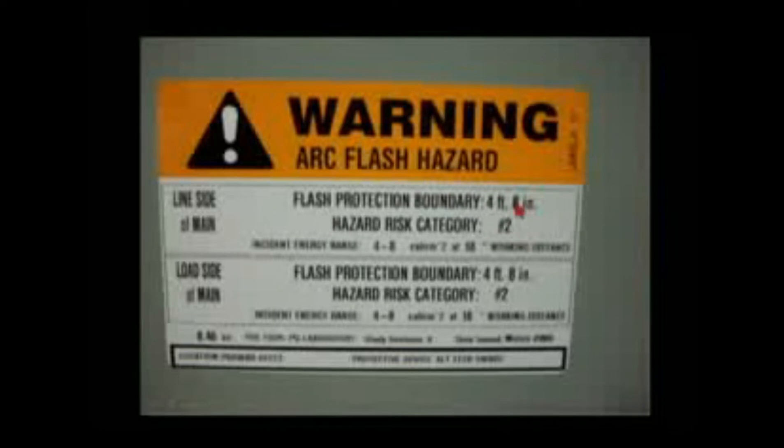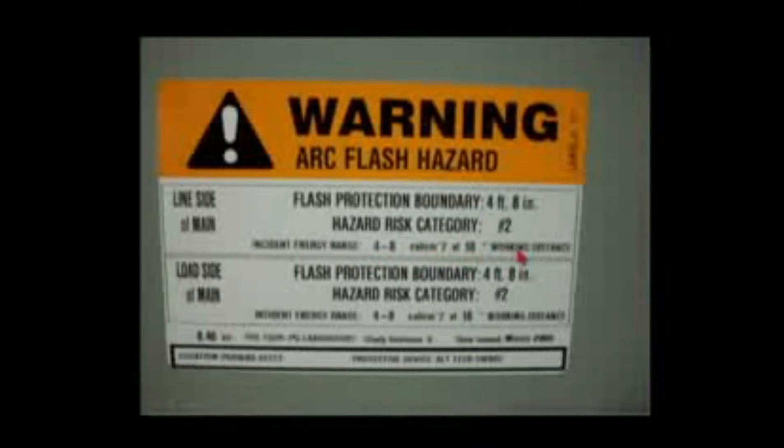The arc flash boundary is in the 70E. There's a risk hazard category number two, incident energy four to eight calories per centimeter squared at 18 inches working distance. This is on the line side; this is on the load side. The problem is, you put an arc flash hazard label on there and nobody understands what that label is talking about.